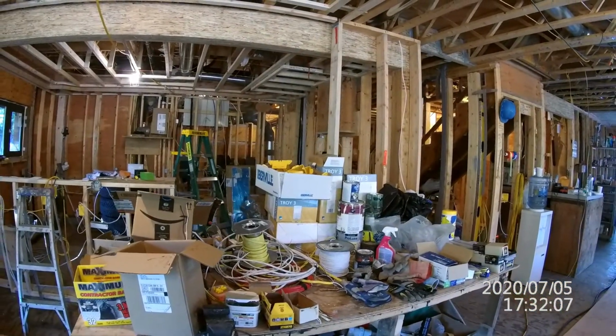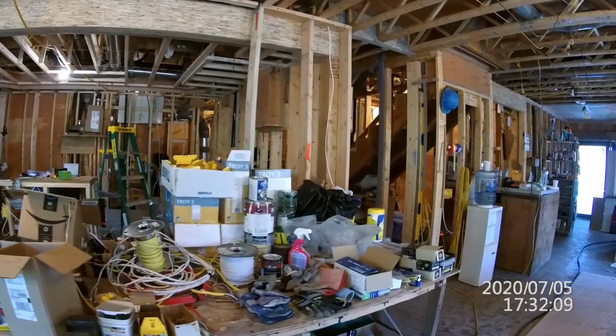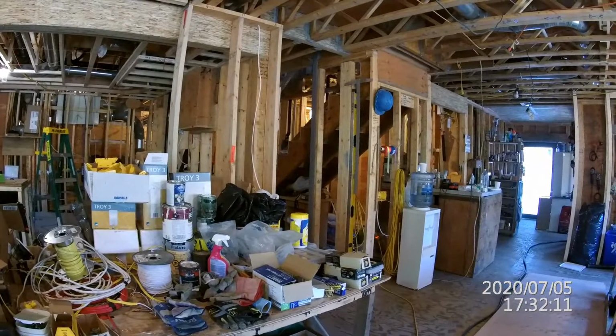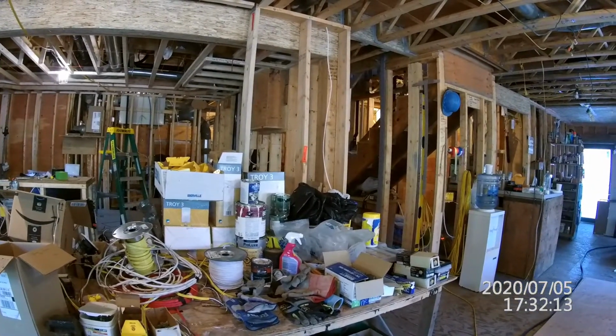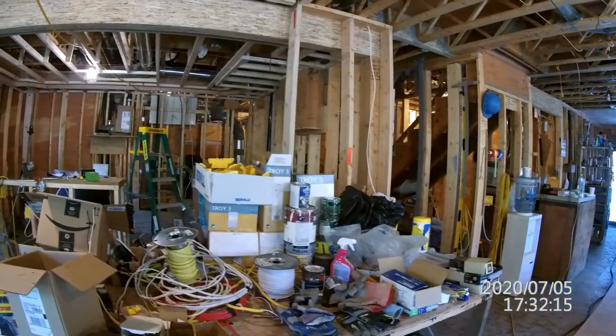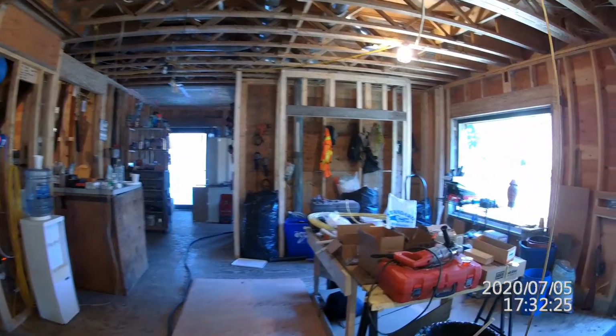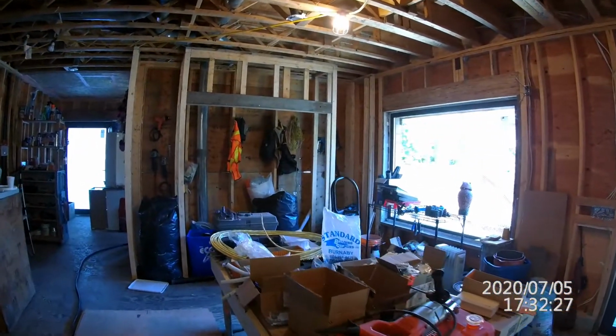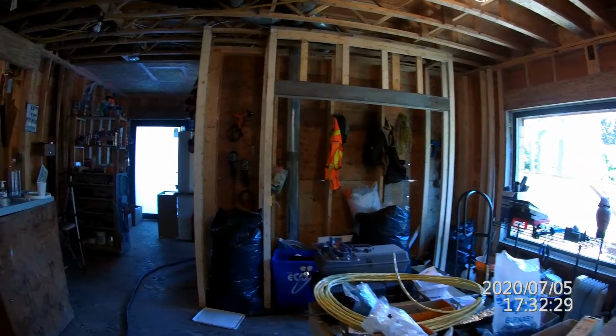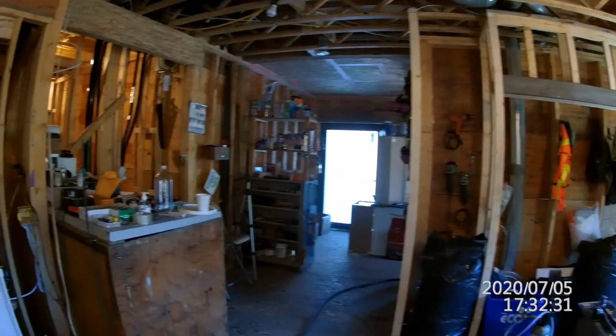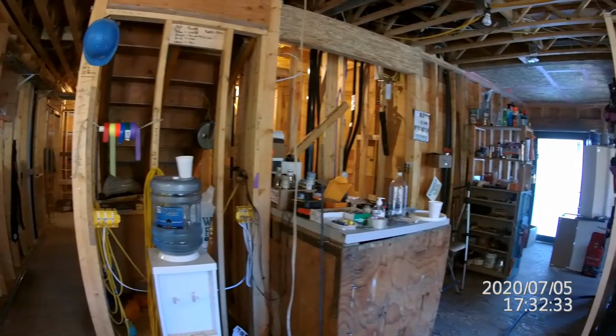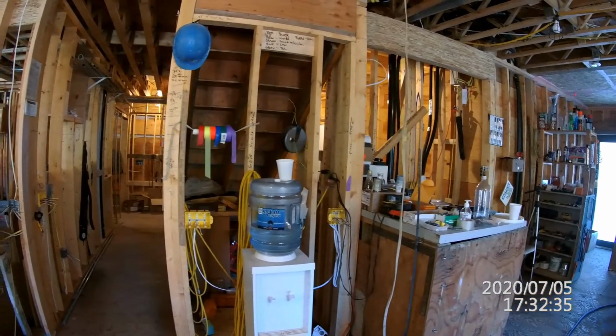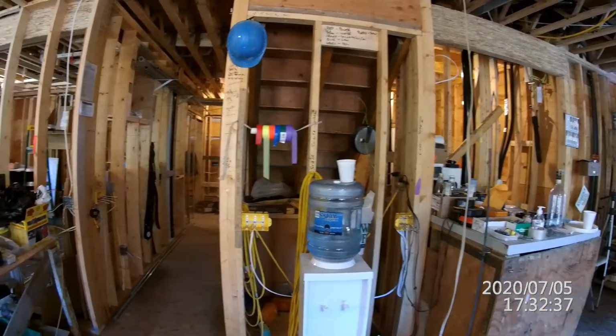Because I'm running centralized DC, I had a big learning curve on what's required to send DC throughout the house. Basically the rule is if it's under 96 watts, it's not that important by electrical code. Once you get above that, you start getting into what are called class 2 and class 1 electrical circuits.